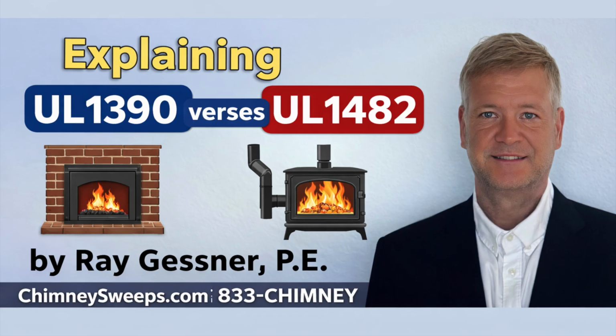Well, if you take the extremely hot pressurized exhaust from a high-efficiency insert and just dump it into a wide, cold brick chimney, those gases undergo rapid expansion. And when a gas expands rapidly in a large space, its temperature drops. Drastically. It cools down way before it can escape the top of the chimney. And when that exhaust cools, the vapor condenses onto the cold brick walls. Oh, and that condensation is creosote, right? Exactly. Creosote is highly combustible. If you vent a modern insert directly into an unlined masonry chimney, you are essentially painting the inside of your home's structural columns with liquid rocket fuel.